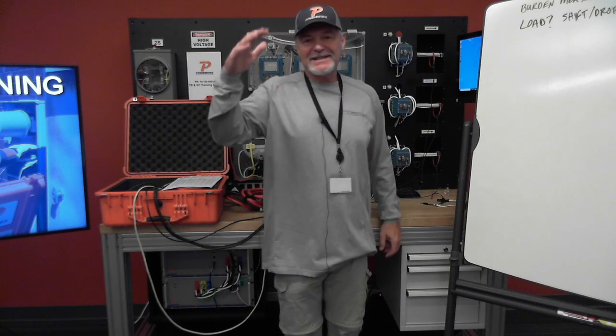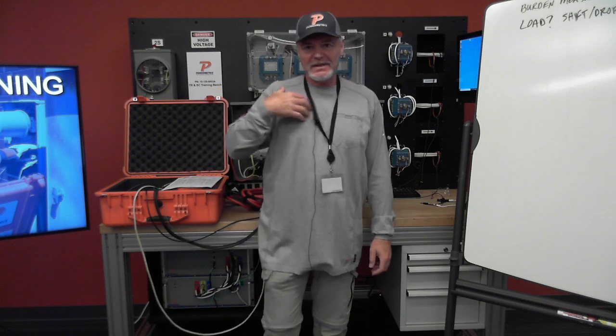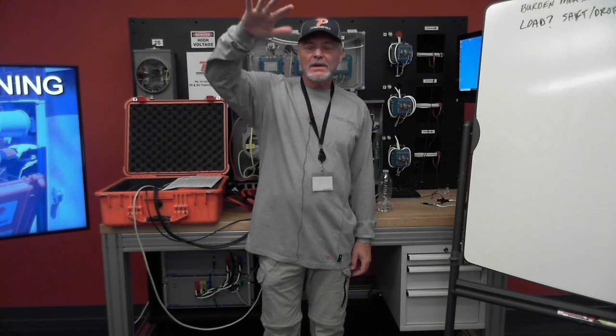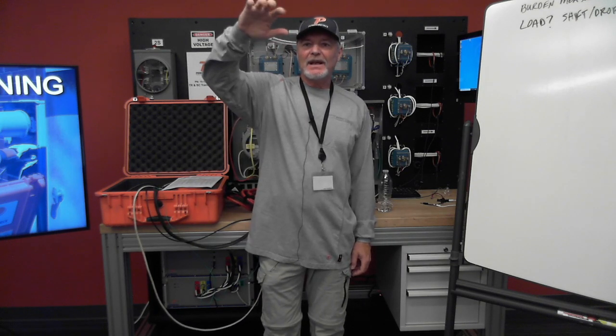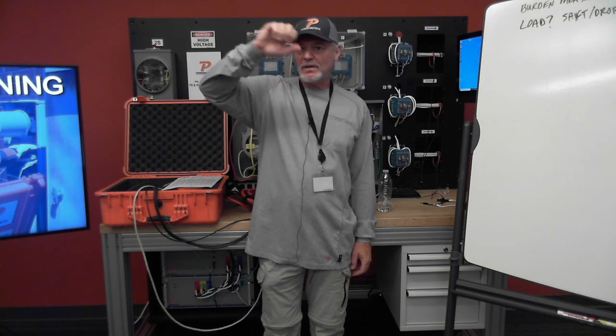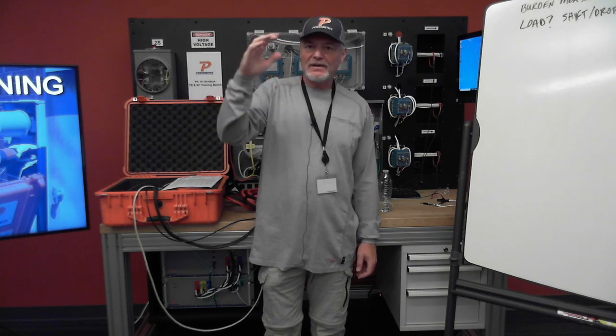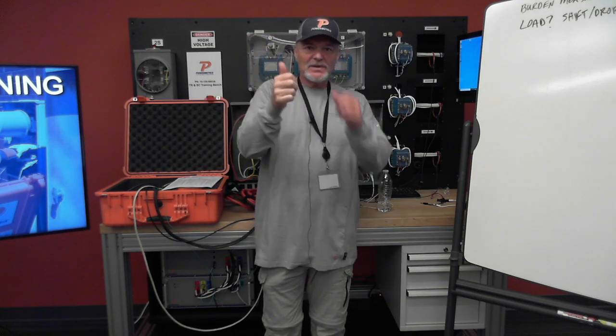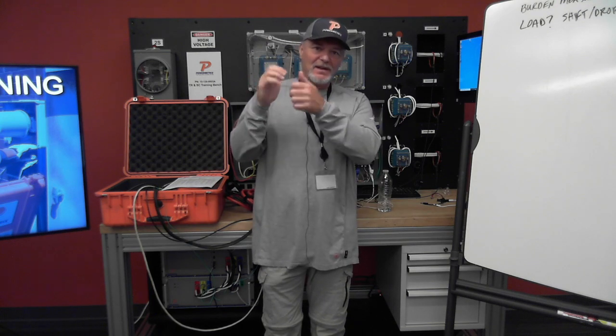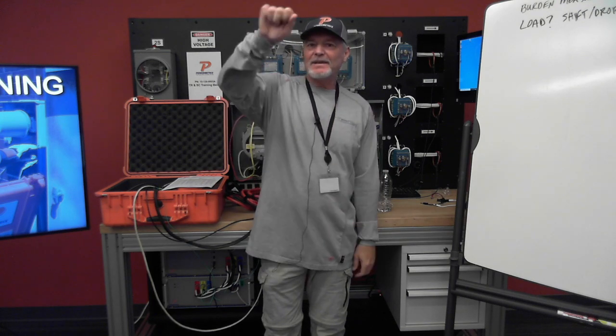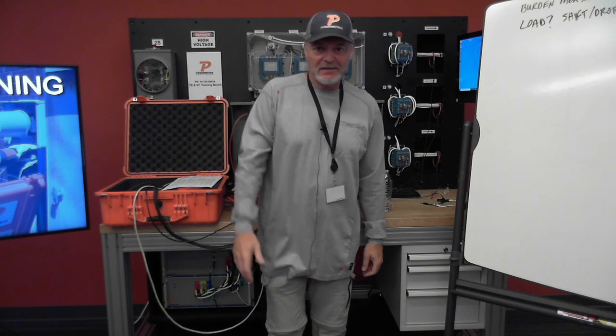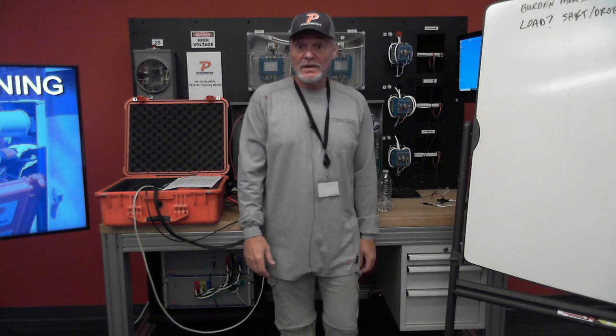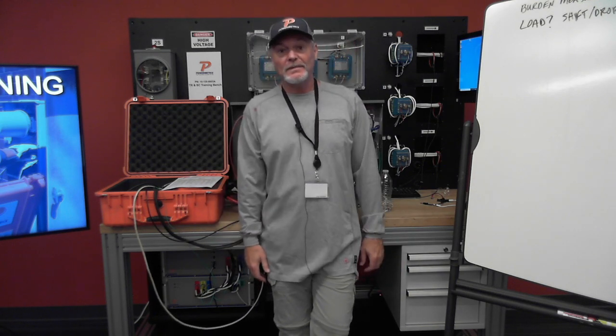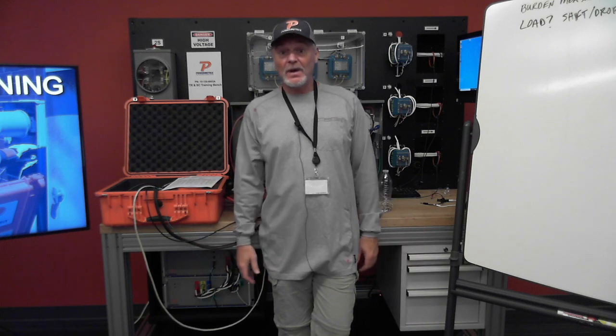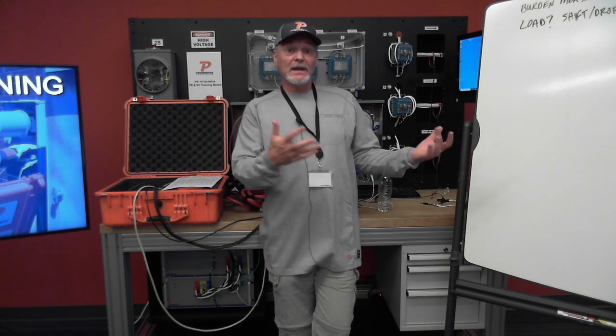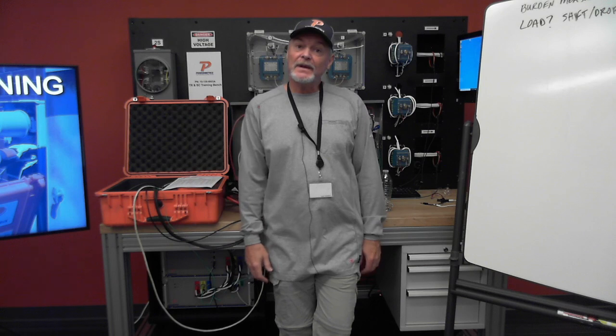Notice it was in stages, which I thought was really interesting. It started out at around 10, and then as we started actuating switches, first we clean, and then it dropped down to 5%. Then we started actuating switches, and it's like 4. Then when we tighten up the screws there on B phase, it comes in below the 3%, which was pass or fail. So it came in, and it was a lot better solution for us than having to get a crew out there and fool with that CT.